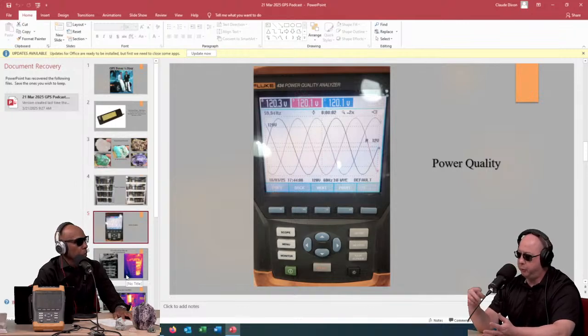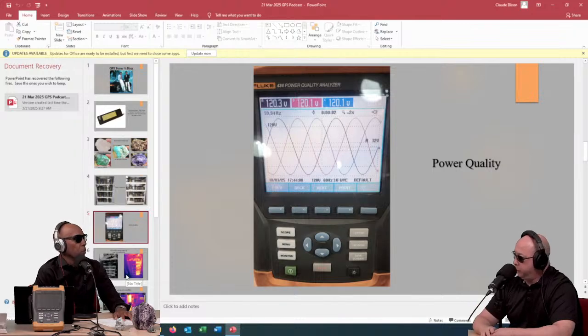Based on how the power is circulating through, from A to C or C to A, depending on how you have the clamps or alligator clips hooked up to the terminals, you can check the rotation both ways. So I don't need a separate meter for that? There are separate meters for that, but this is an all-in-one that does the amperage, phase rotation, and your voltages.